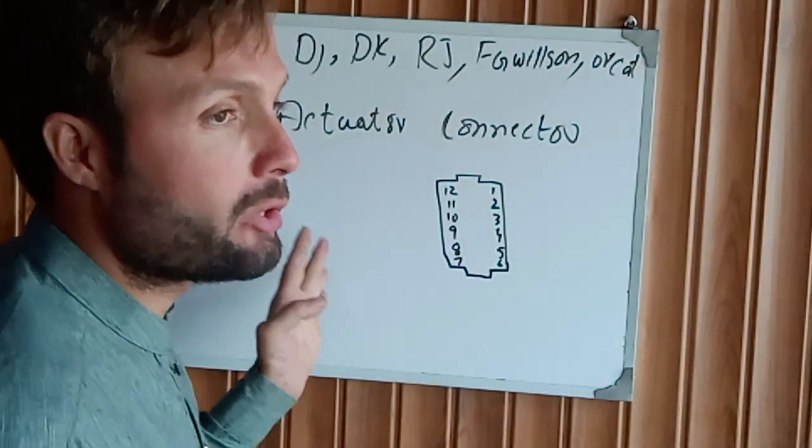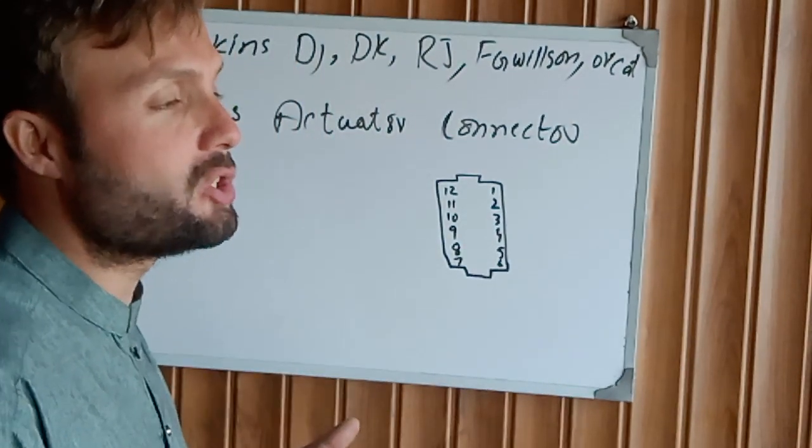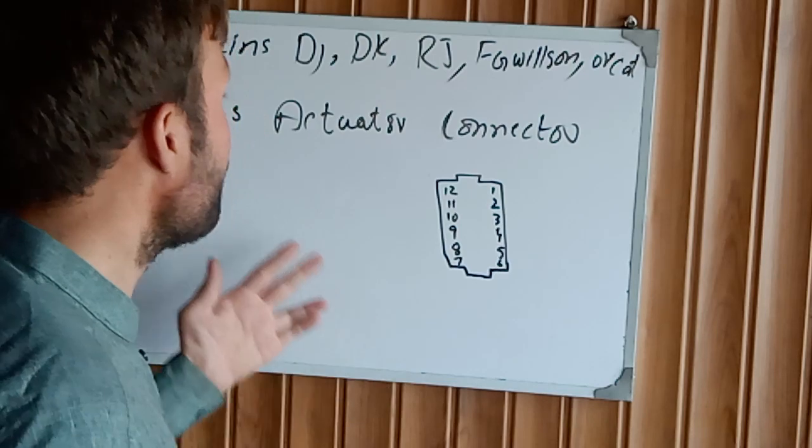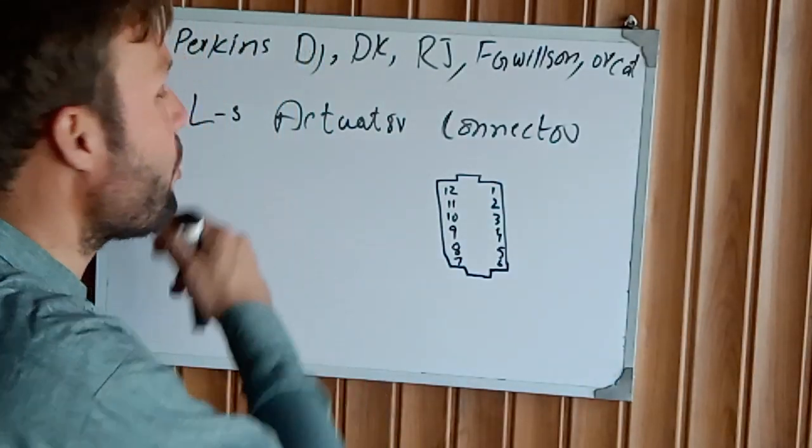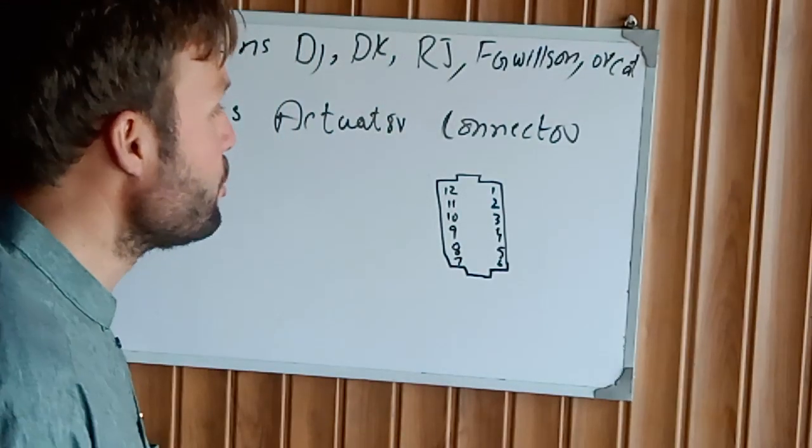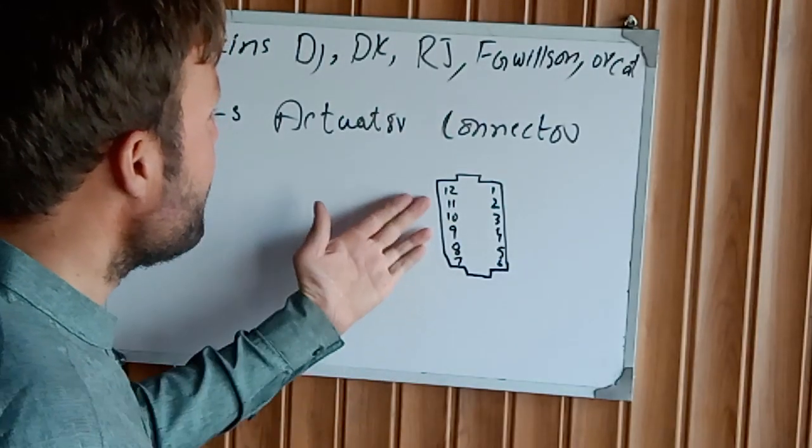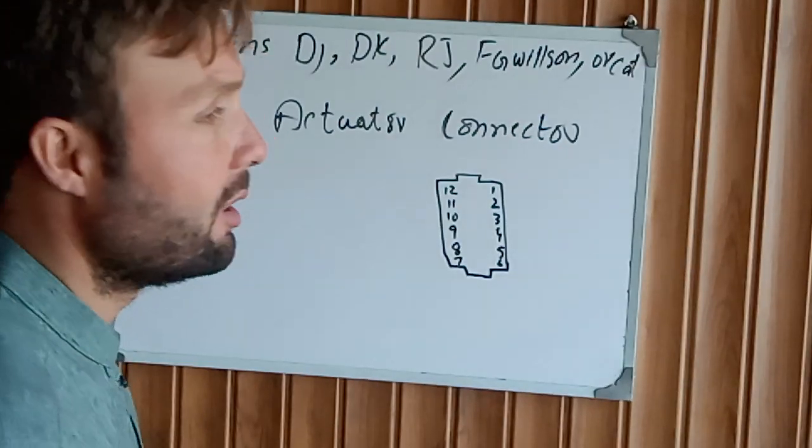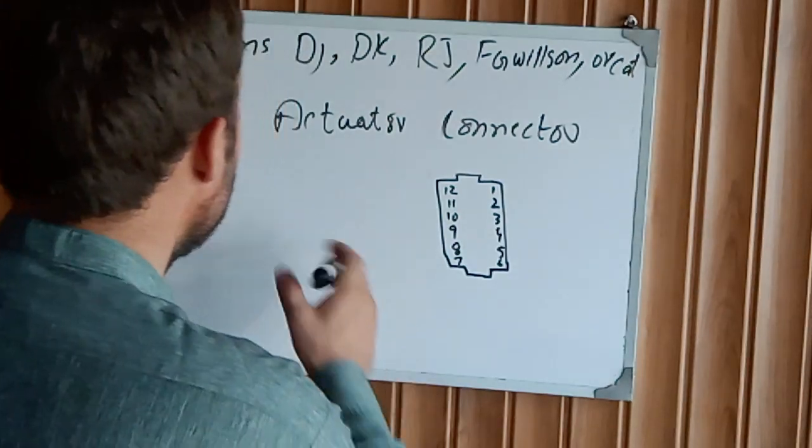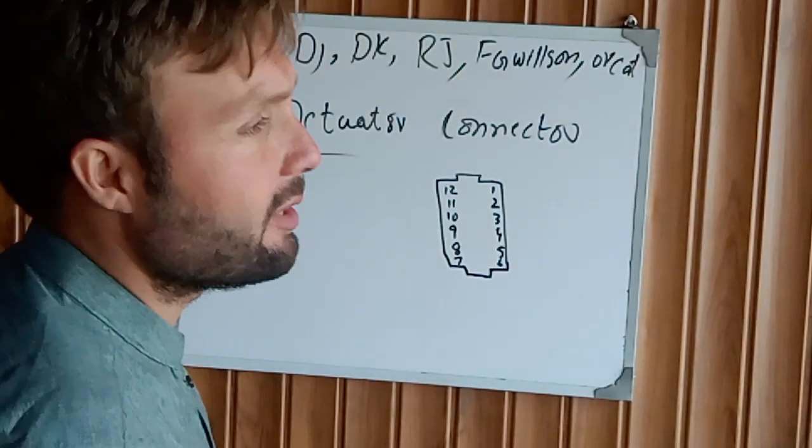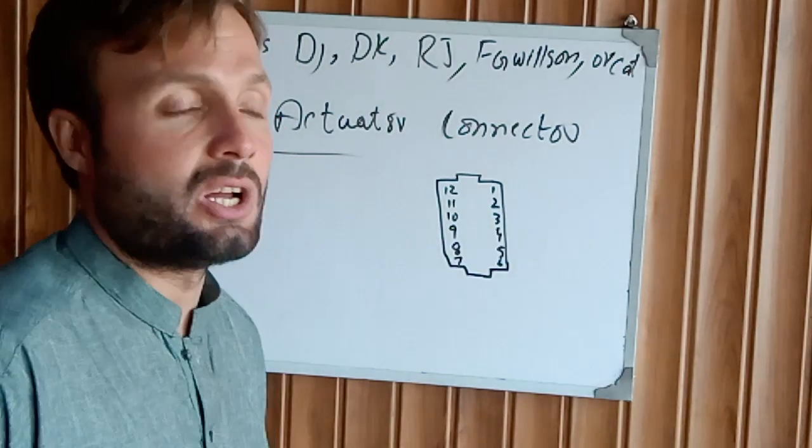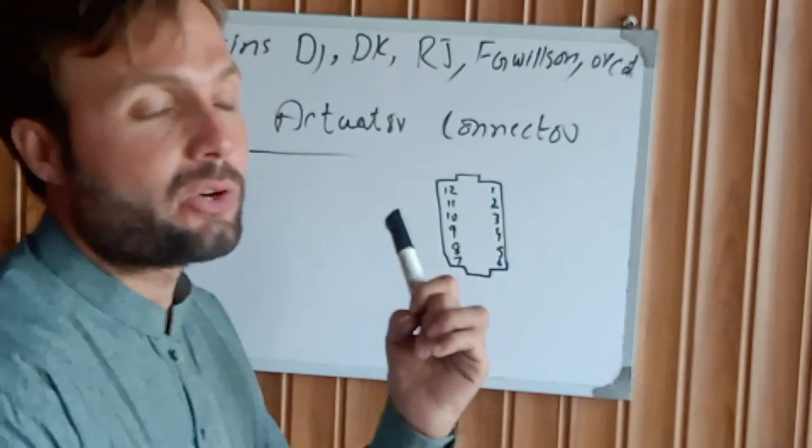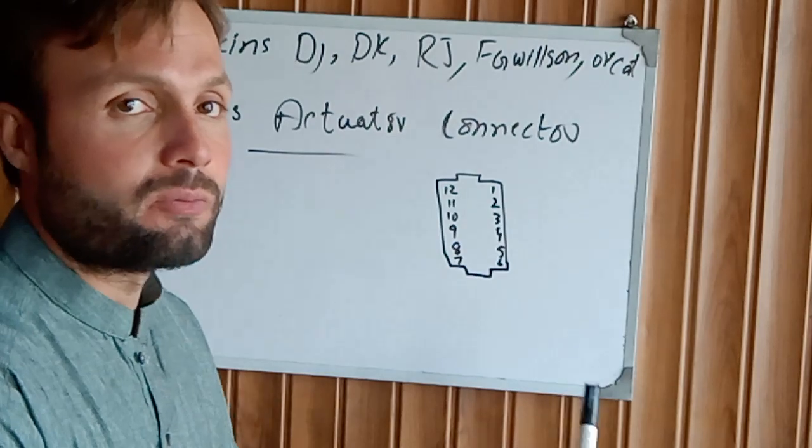A lot of times this causes problems on Perkins DJ, DK, RJ engines for 100-110 kVA generators - engine cranks but does not start. How to know, install, fix, and test if this actuator is working properly? If you have this problem, that means your engine cranks but does not start. First of all, check the fuel supply.